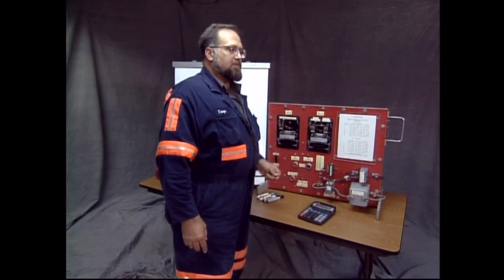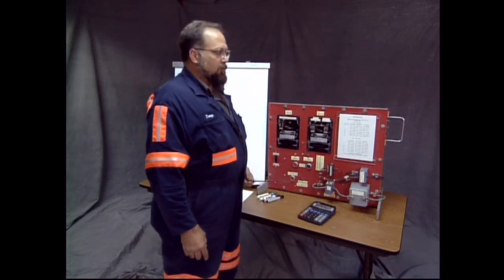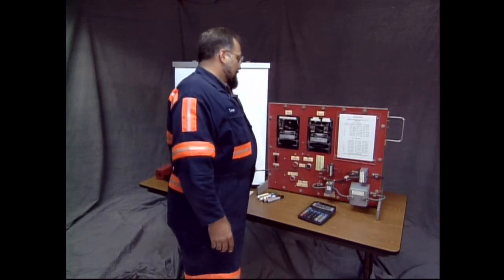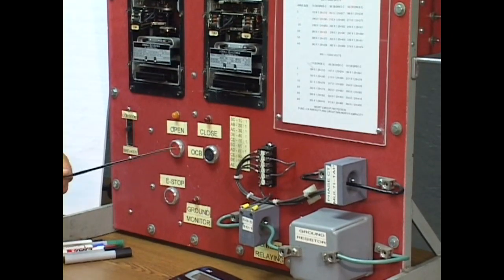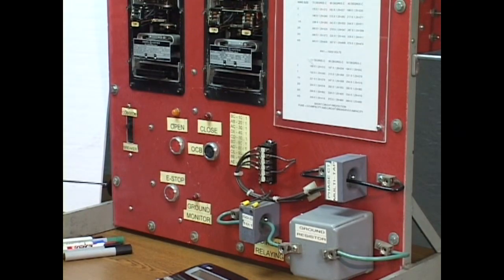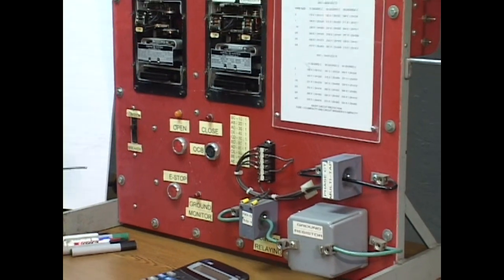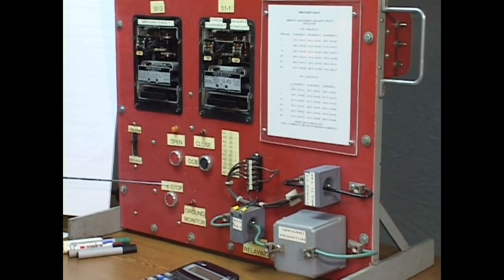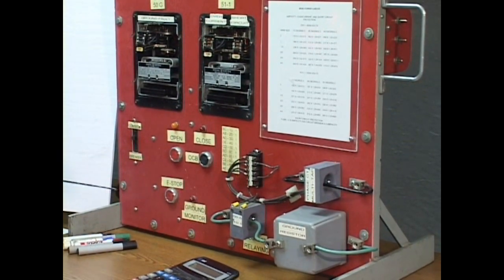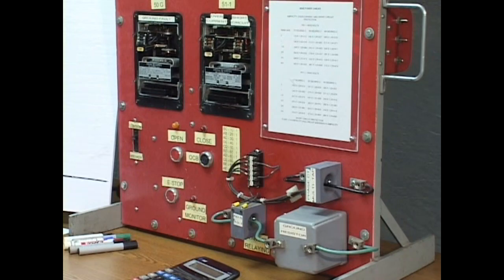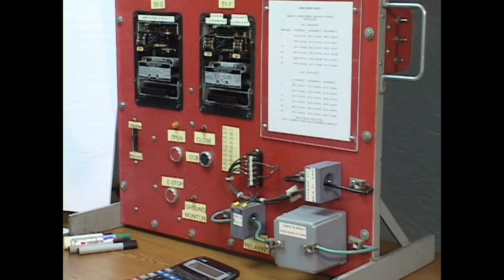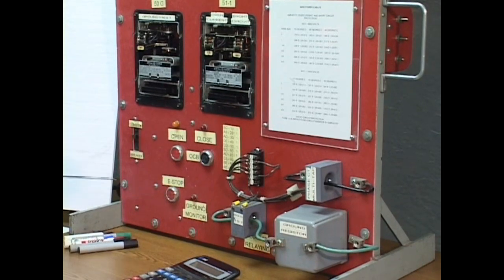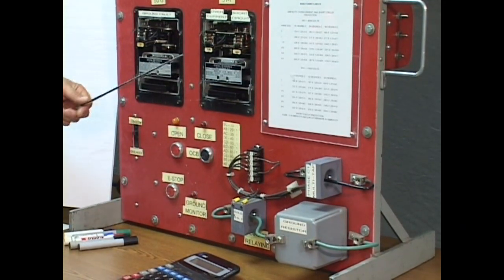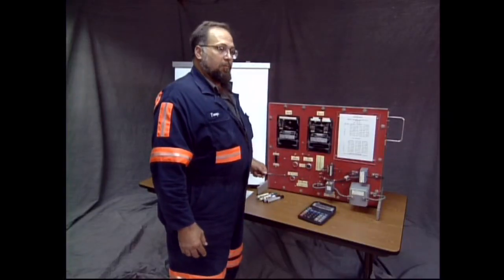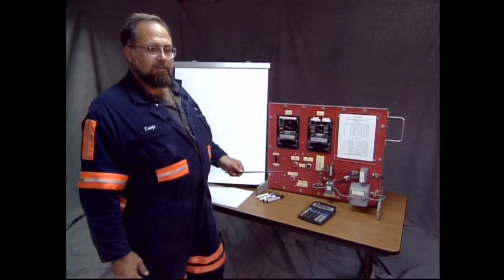And each one of those boxes, each one of those high voltage installations, be it a belt transformer, section power center, pump transformer, whatever, will have the ground monitor routed through the box, through an e-stop, and then through various lid switches on the box to control the unauthorized opening of a box, or to give you an ability to turn all of the power off at one time. When you push the e-stop, you're breaking the continuity of the ground monitor. The ground monitor controls the UV or the shunt trip, and the shunt trip and UV control the OCB or vacuum breaker. Oil circuit breaker, UV is under voltage release.